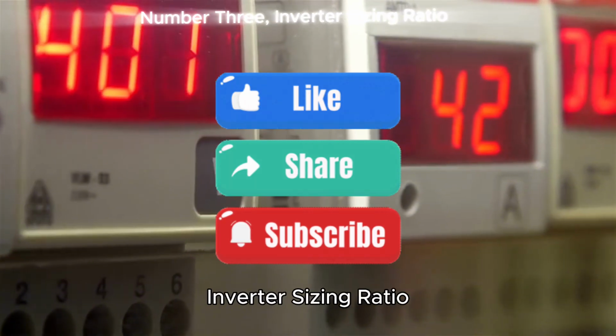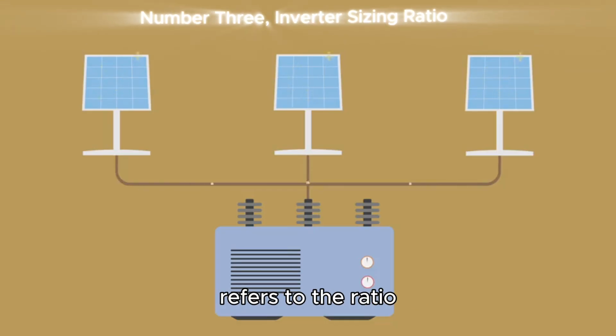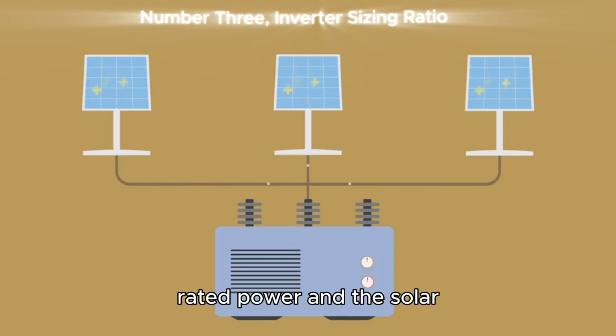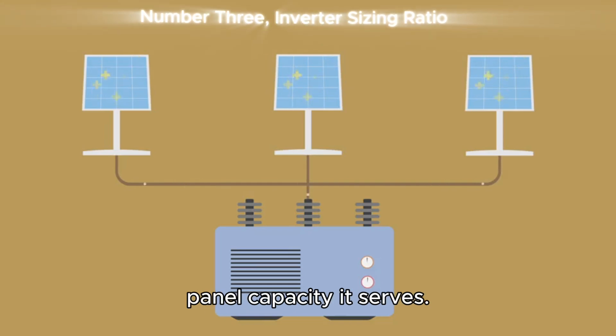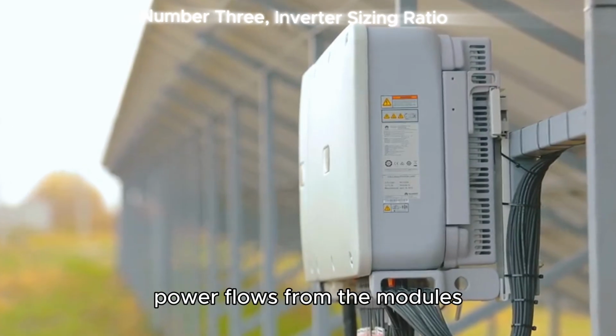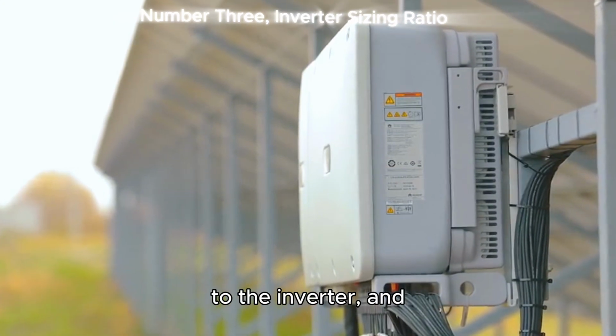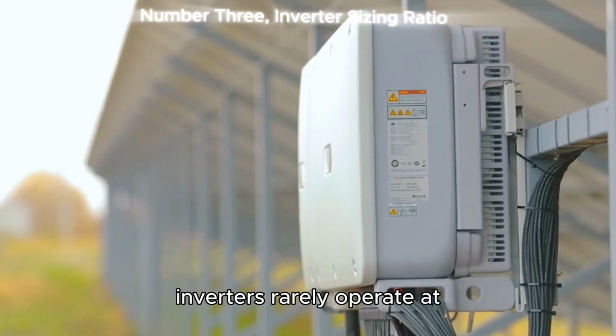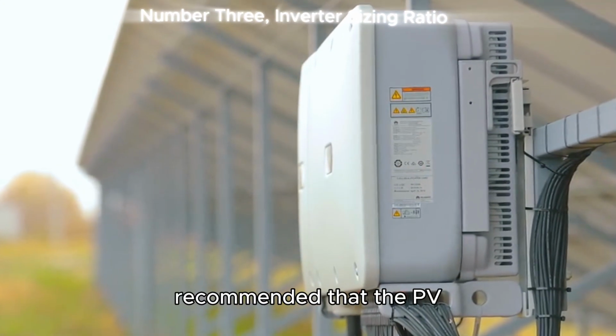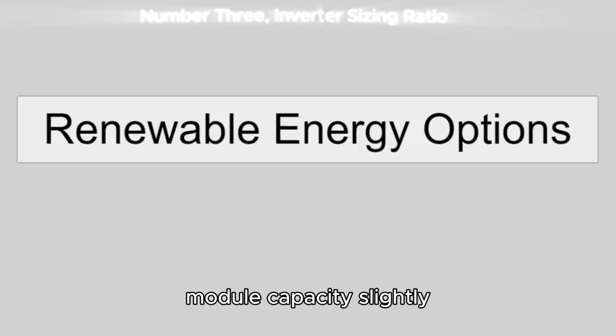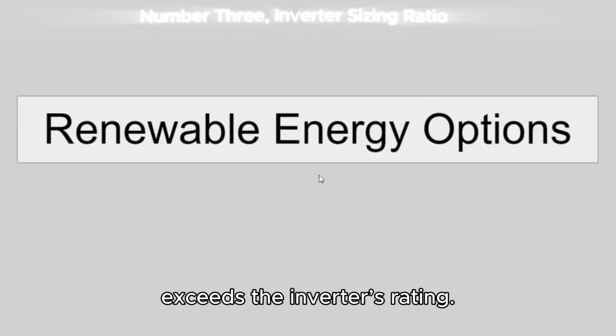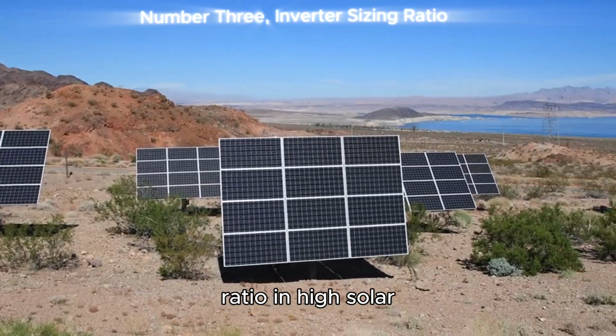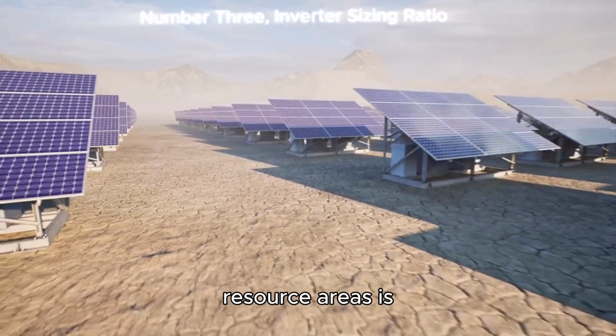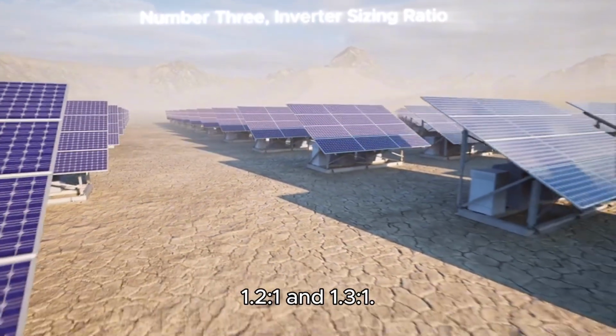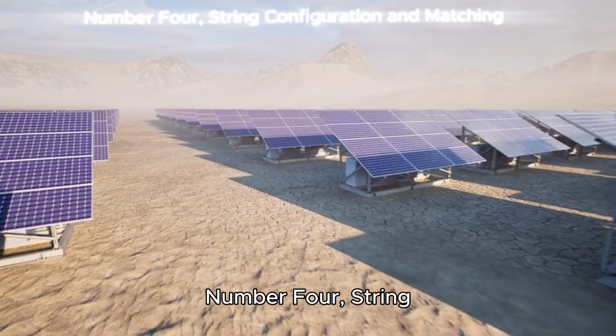Number 3. Inverter sizing ratio. The inverter sizing ratio refers to the ratio between the inverter's rated power and the solar panel capacity it serves. Since energy losses occur as power flows from the modules to the inverter, and inverters rarely operate at full capacity, it's recommended that the PV module capacity slightly exceeds the inverter's rating. An optimal design ratio in high solar resource areas is generally between 1.2:1 and 1.3:1.